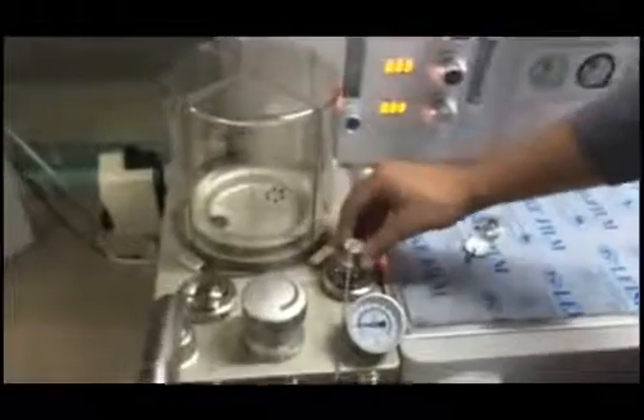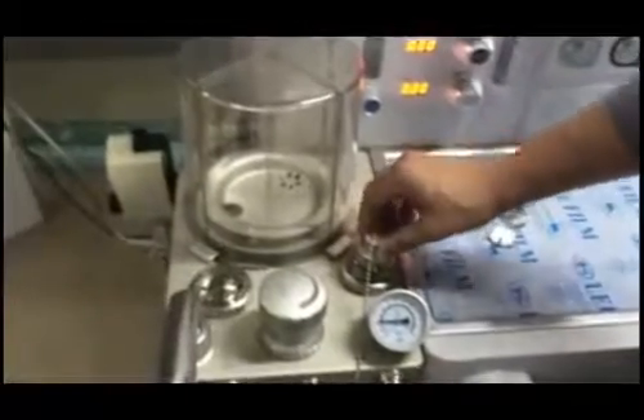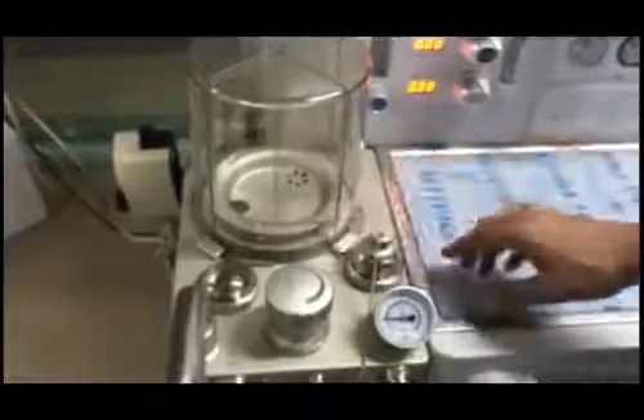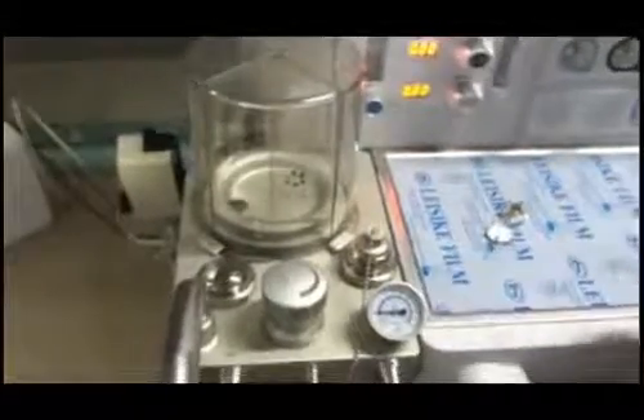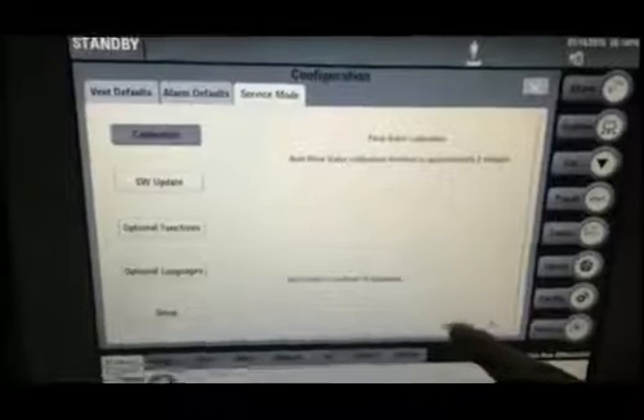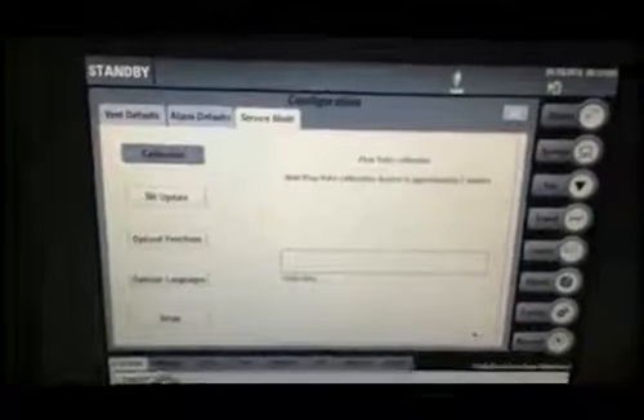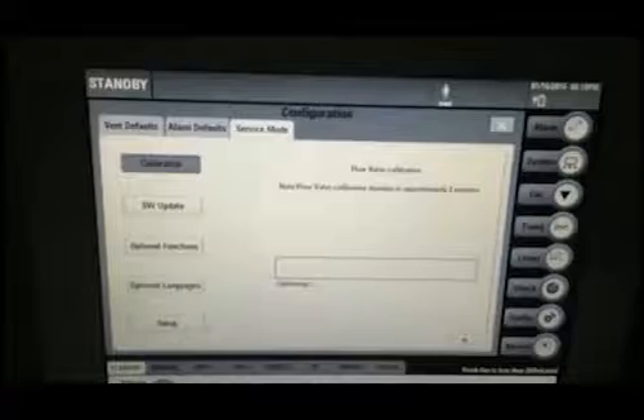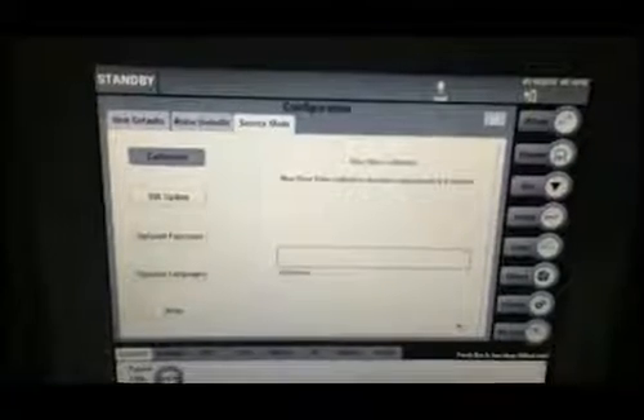If the product you have purchased has an oxygen sensor, you do not need to remove it during this calibration. After you have completed these steps, please press the start button. Note that the flow valve calibration approximately takes 2 minutes. After this instruction, please press the start button again. Please do not disturb the product during the calibration process.